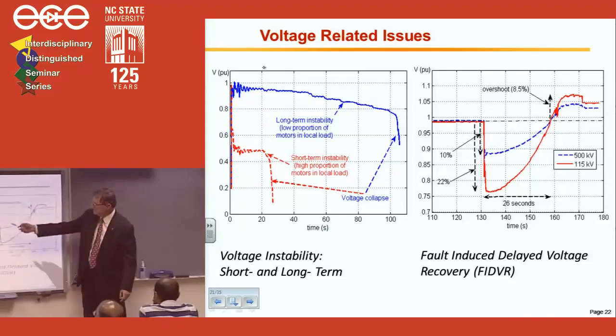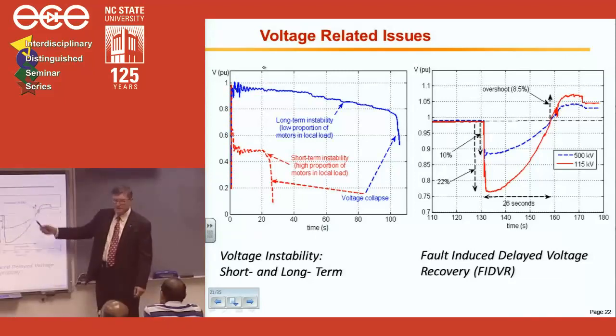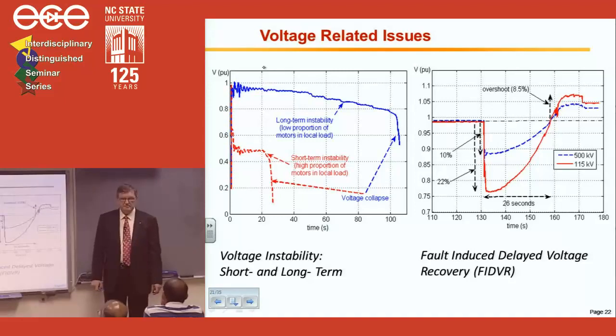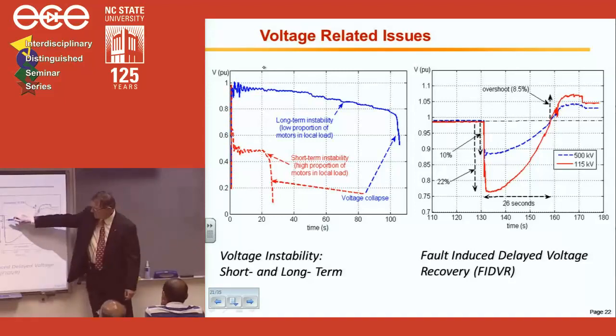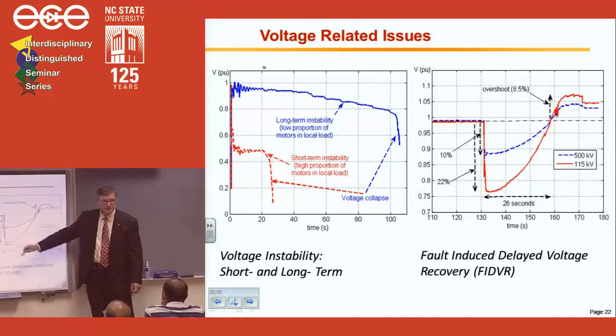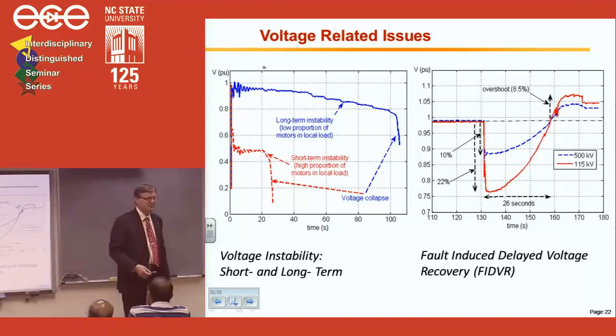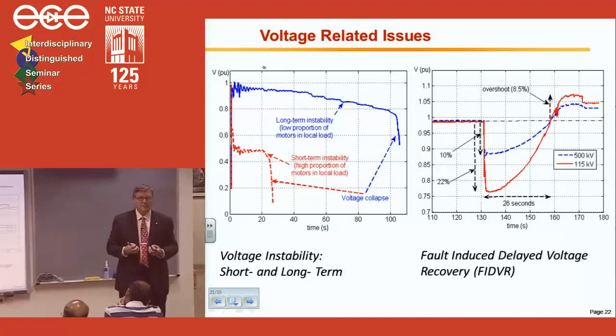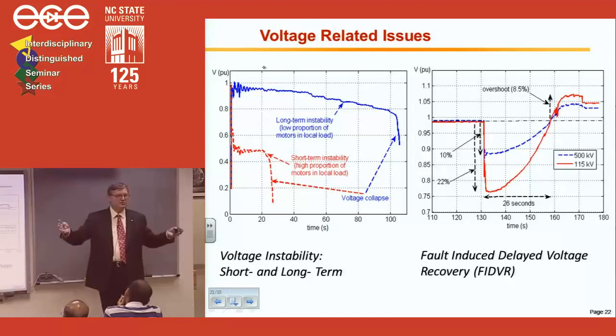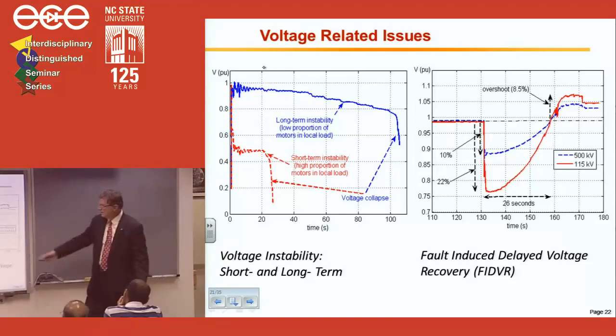What happens is you have a fault, and voltages get depressed due to the fault. As voltage goes down, motors start stalling, but they don't trip, so they draw reactive power. Once the motors trip, because they may trip on some thermal protection or whatever, suddenly you have overshoot.